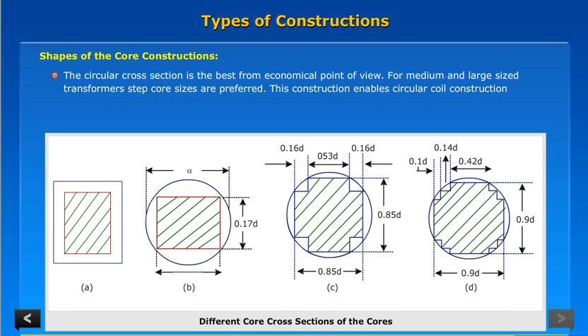The circular cross section is the best from an economical point of view. For medium and large size transformers, step core sizes are preferred. This construction enables circular coil construction.